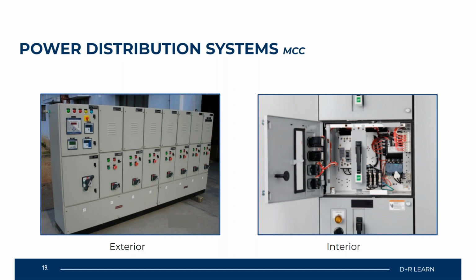Now, with these MCC systems, you will find a lot of your motor systems that are used with HVAC applications connected directly to these MCC panels. And if you look at this image to the left very clearly, a lot of the time each one of these sections of the MCC will be allocated to maybe one motor. Depending upon your manufacturer or your vendor, you have different options available to you, such as an LCD screen that might be showing you the energy characteristics of that motor system as it's running in operation.